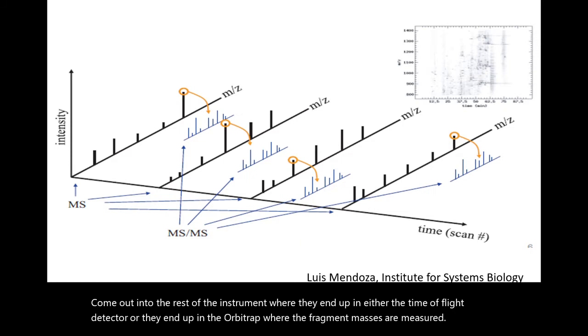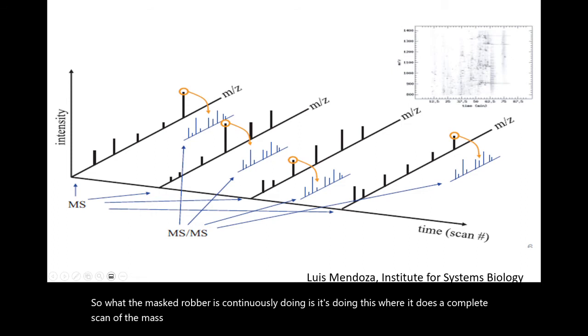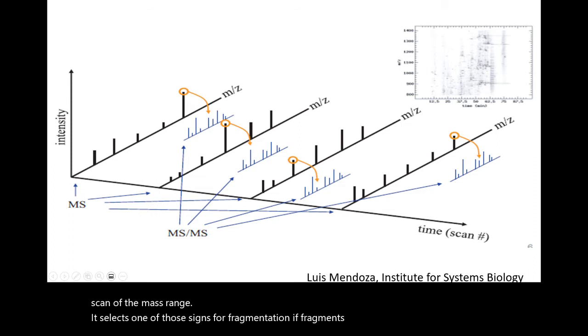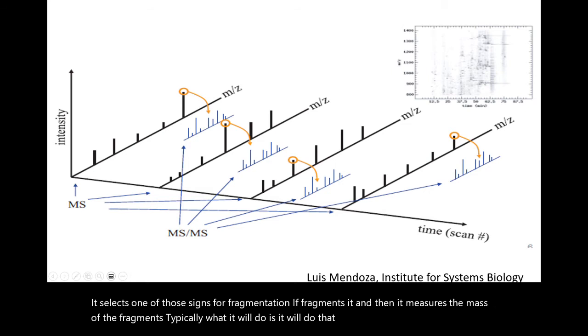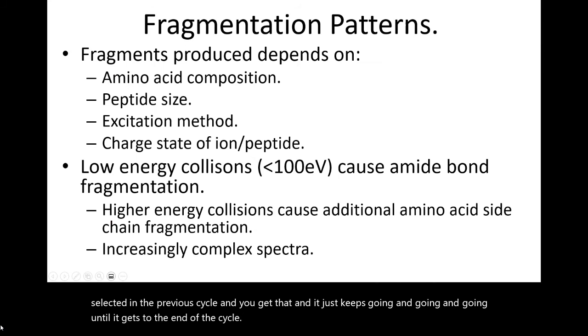The mass spectrometer continuously does a complete scan of the mass range, selects one of those ions for fragmentation, fragments it, and measures the masses of the fragments. Typically it does this for all ions in an MS1 scan, then does another MS1 scan, selects the most intense ion not previously selected, and keeps going until it gets to the end of the cycle.